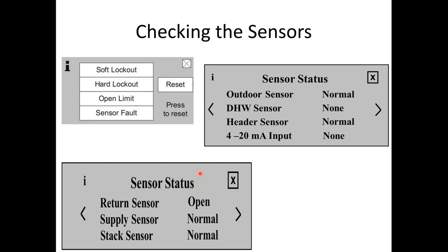Or we can go right through our control, and our control will kind of tell us what's going on with the sensors. We'll have sensor status, and it will tell you whether it's open, normal, what's going on with it. Usually doesn't lie. If it's not plugged in, it'll definitely be open. If you're 4 to 20 milliamp, if you're doing remote modulation or allowing a tekmar or control to modulate the boiler, we'll have to set it for that, but it'll come set for none.